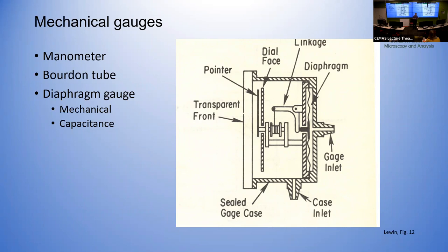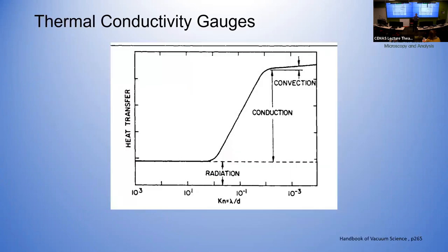So the Bourdon tube, basically, you have your vacuum here at the bottom, and it's attached to a flexible tube. As you change the pressure coming in, that tube will deflect, and it moves the needle on the arm, just mechanical linkage. The diaphragm gauge is somewhat similar. You have your vacuum here coming in on the right, and you have a diaphragm that deflects as you change the pressure. And again, you have a mechanical linkage to change a needle on a gauge. Now the capacitance gauge is very slightly different. You're again looking at the deflection of the diaphragm, but now you've metallized one side of the diaphragm, and it becomes one side of the capacitor. So you can measure electrically. You can measure the capacitance very precisely and do better than a mechanical linkage. So that's why it has a lower ultimate pressure range.